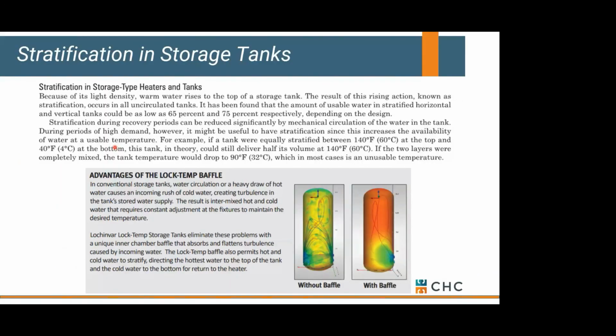I mentioned this briefly, but one thing we're trying to maintain in a storage tank is some level of stratification. We're trying to keep our hot water near the top of this tank. And as cold water comes in from our city, it's going to pick up this hot water and send hot water out to our system. How do we do that? Most tanks are going to have some type of baffle installed, and that baffle tries to keep this stratification or turbulence within the tank as low as possible.